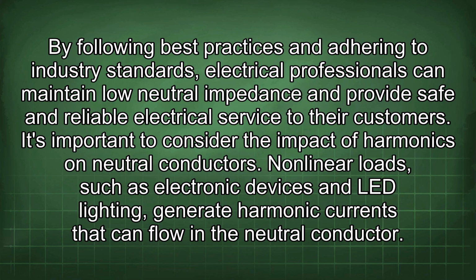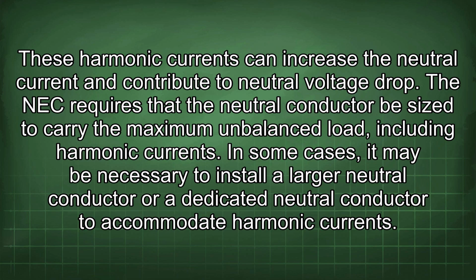It's important to consider the impact of harmonics on neutral conductors. Nonlinear loads, such as electronic devices and LED lighting, generate harmonic currents that can flow in the neutral conductor. These harmonic currents can increase the neutral current and contribute to neutral voltage drop. The NEC requires that the neutral conductor be sized to carry the maximum unbalanced load, including harmonic currents.